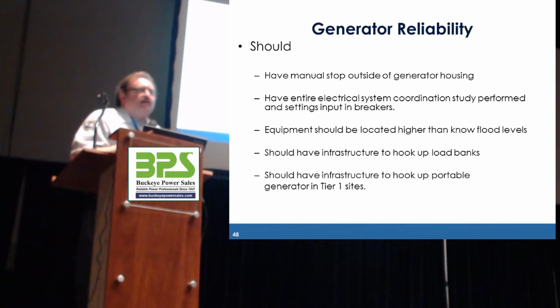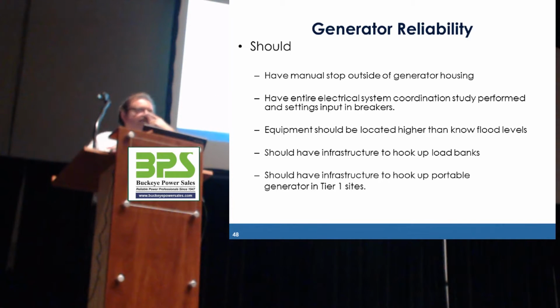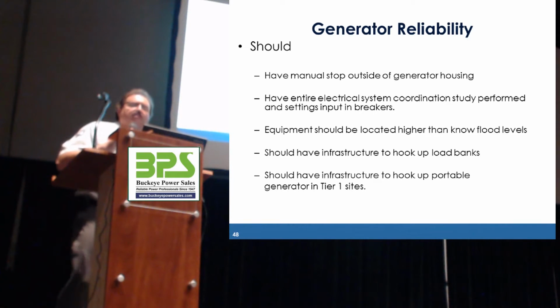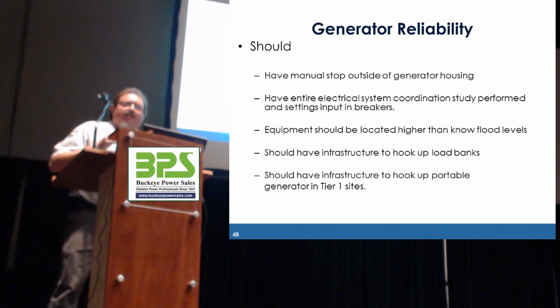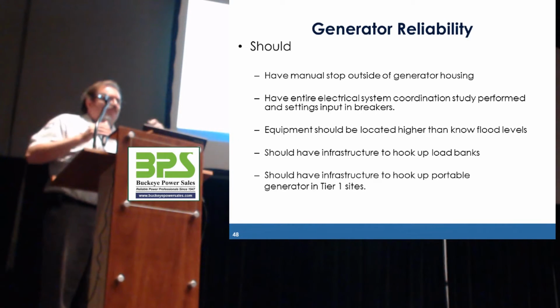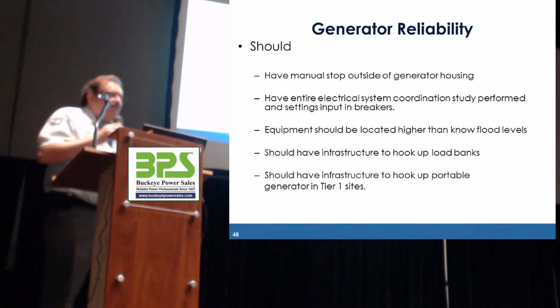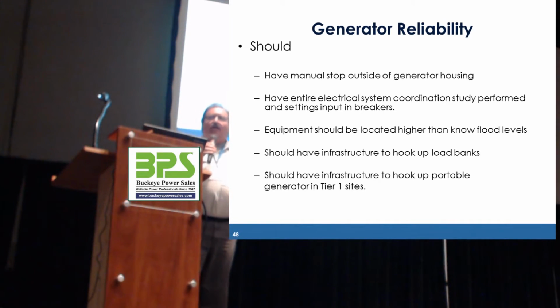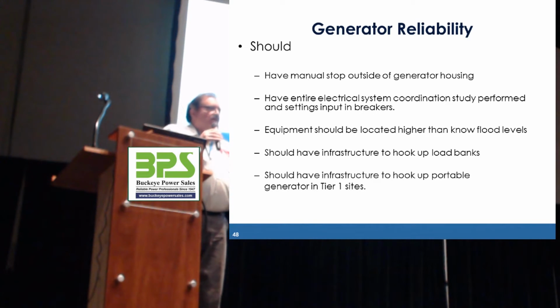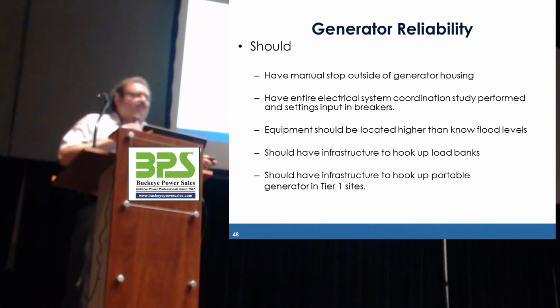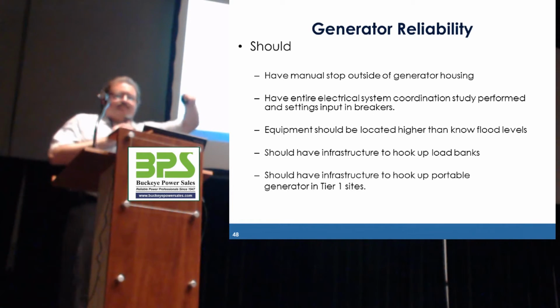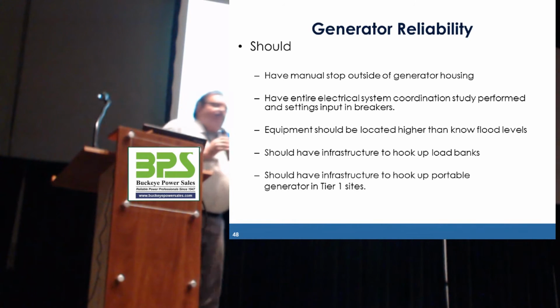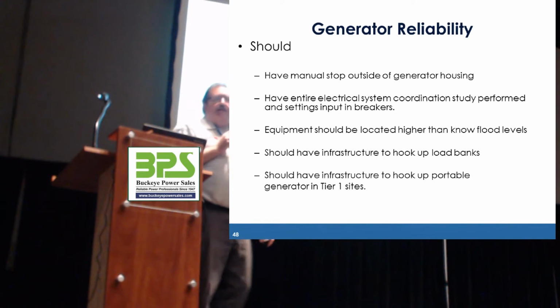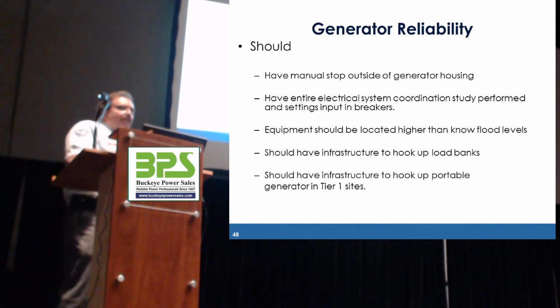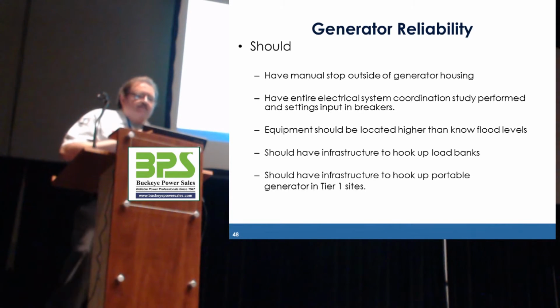So the shoulds that they recommend, again, these are just if you want to take it to that level to make sure to try to alleviate all issues. One of the shoulds is that there should be a manual stop of the generator outside of the generator housing, and preferably away from the generator. Now, the chances of your generator ever catching on fire are extremely, extremely slim. But if Rocky Raccoon gets into the generator while it's running and it's getting ugly, you don't want to have to get into that housing to shut that generator off, right? So you should have a remote stop, the ability to stop that generator from someplace else.